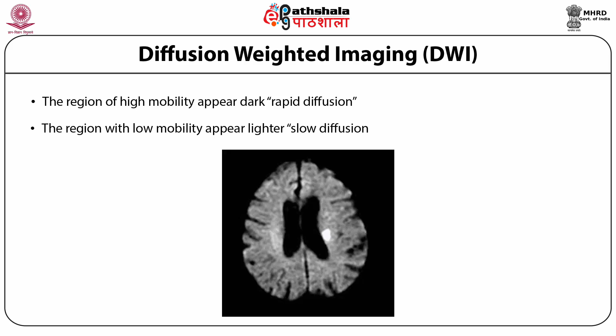The MRI uses the magnetic spin property of protons of hydrogen to create images. To obtain a diffusion weighted image, a pair of strong gradient pulses are added to the pulse sequence. The first pulse dephases the spins and the second pulse rephases the spins if no net movement occurs. If net movement of spins occurs between the gradient pulses, signal attenuation occurs. The degree of attenuation depends on the magnitude of molecular translation and diffusion weighting. In this figure, the region of high mobility appears dark, representing the rapid diffusion, while the region with low mobility appears lighter, representing the low diffusion of a multi-compartment system.